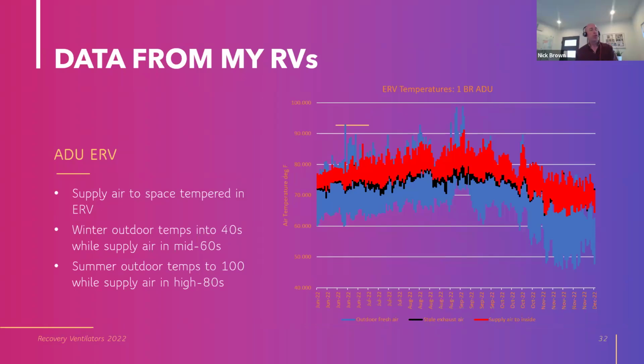Here are the temperatures to show you the heat tempering of the outdoor air. This is June to December in the ADU. It's a 1-bedroom. And the outdoor fresh air temperature is shown in blue. So you can see it's going almost to 100 at the end of August. It's going down below 50 in November. That's the Long Beach climate. And the supply air to the inside is shown in red. Notice how much less extreme that is, right? So there's the tempering shown in graphic form.